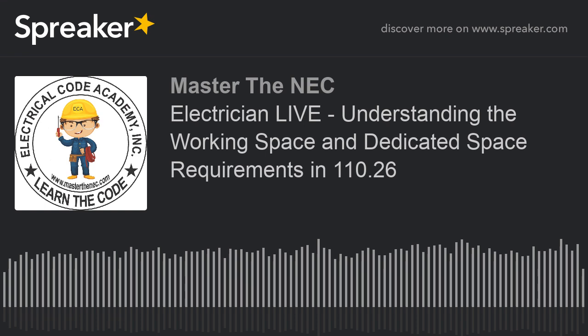Now, the key thing that I'll point out here is that it says where the equipment is rated 800 amperes or more. Interestingly enough, we could meet the rules to have the two separate entrances at each end of the equipment. But remember that example where I said we had a 600 amp 4 foot wide and we had two of them in a room, and combined it was 1200 amps or more, and combined it was 6 feet or more, and that triggered the two entrance and egress. Here, the personnel door requirement seems to say where the equipment is rated 800 amperes or more. It doesn't say where combined it is 800 amperes or more.